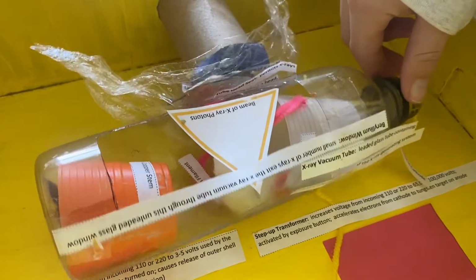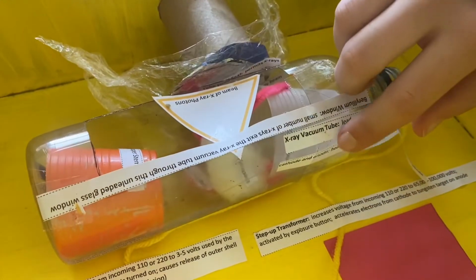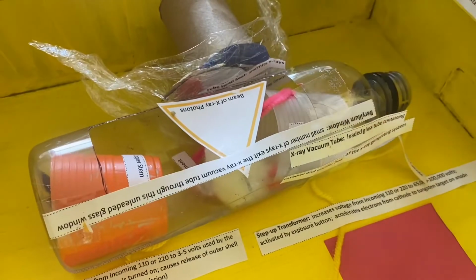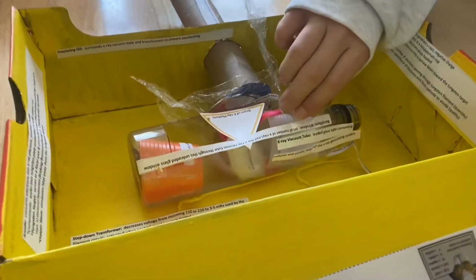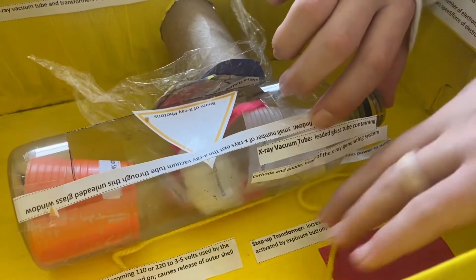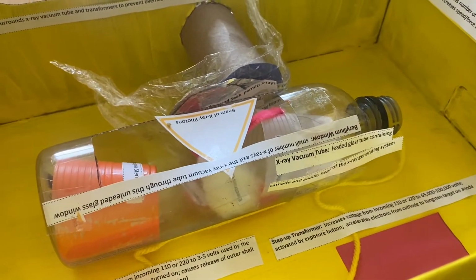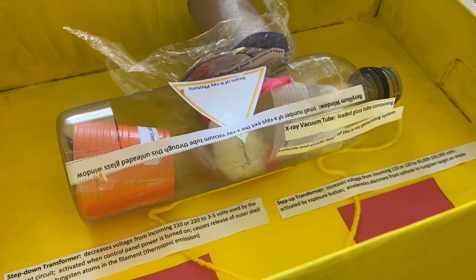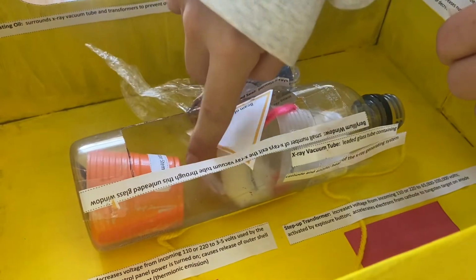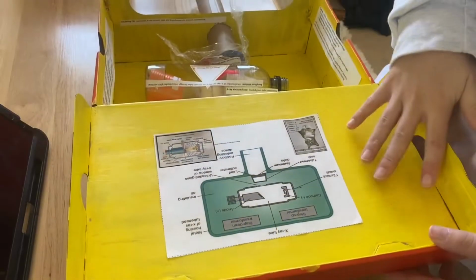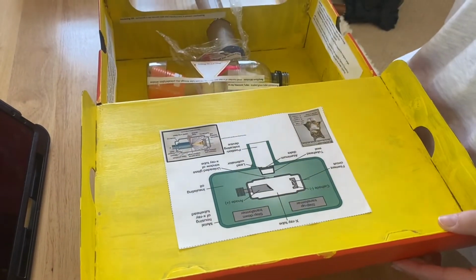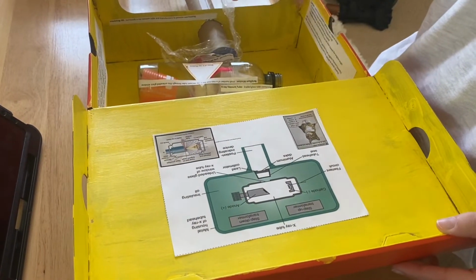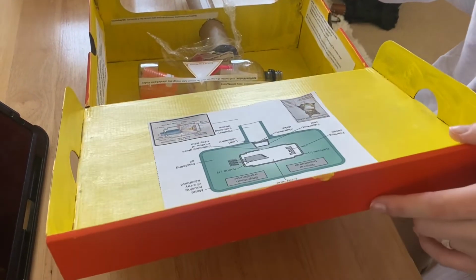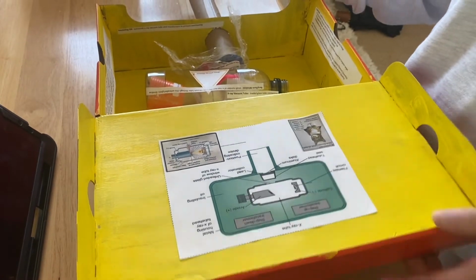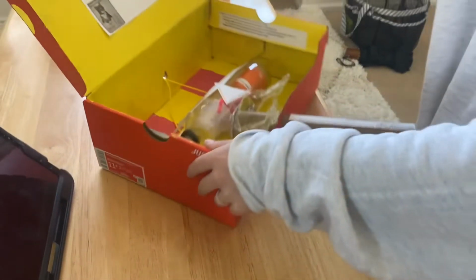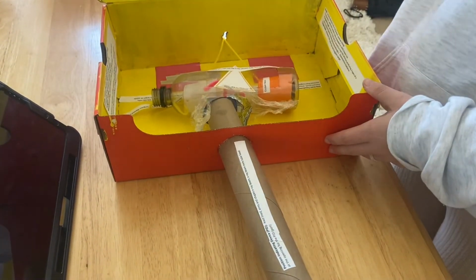And then let's look right here. We have the X-ray vacuum tube, a leaded glass tube that contains the cathode and anode, the heart of the X-ray generating system. So what's represented on both of these sides would actually be within this. We have this string that comes in here, which is representing the filament circuit, and that provides power to the tungsten filament in the cathode. So again, the tungsten target is there. And last but not least, as we can see, there's a covering of yellow paint throughout this, and that's actually representing the insulating oil that surrounds the X-ray vacuum tube and transformers, which prevents overheating. And that is my full presentation on how X-rays are produced and of my tube head.